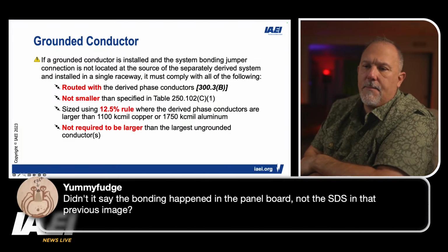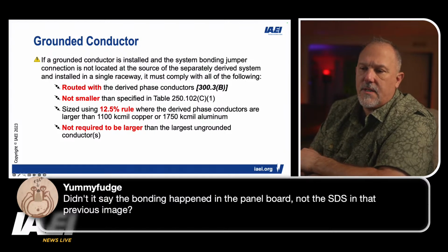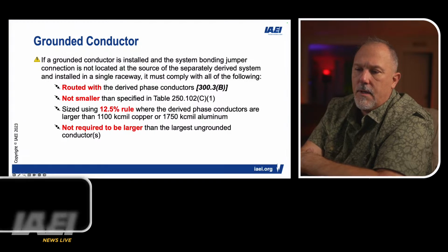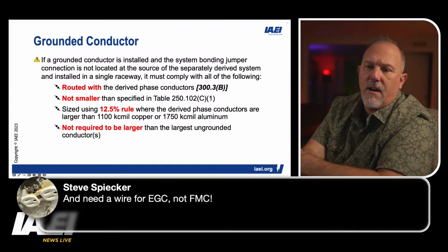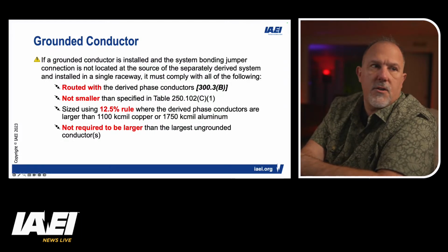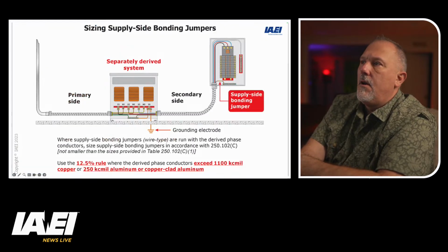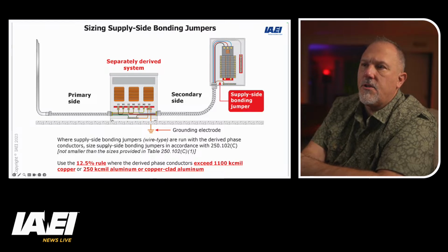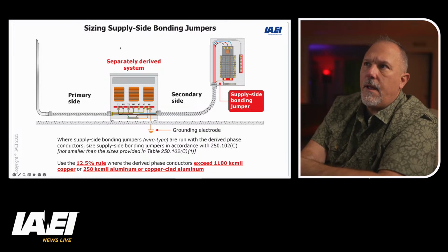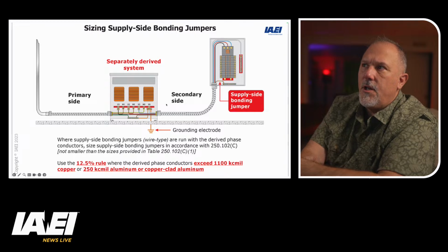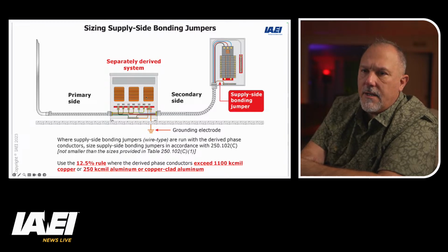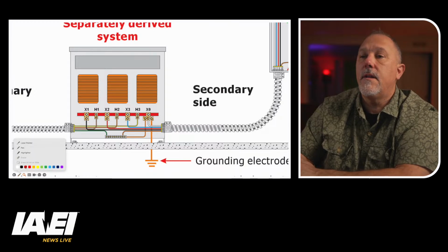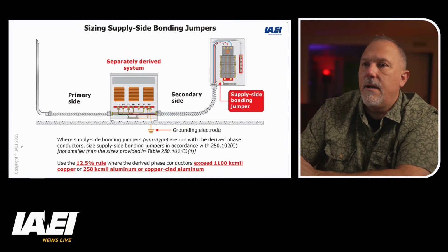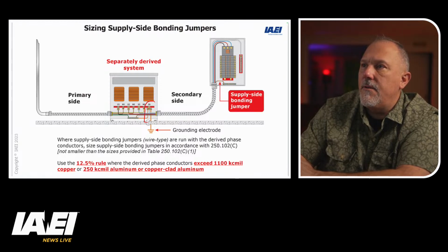Didn't it say the bonding happened in the panel board, not the supply side, in that previous image? I'm going to take a look at that image. Hold on. Steve says, and need a wire for the EGC. Yeah. So let's go back to that image. There's your supply side bonding jumper, where supply side bonding jumpers are run with the derived phase conductors. So this is your separately derived system, and the bonding is done right inside this panel. I don't know if I can do this. I clicked the wrong one, but I still got the right thing there. So there is bonding done right here.